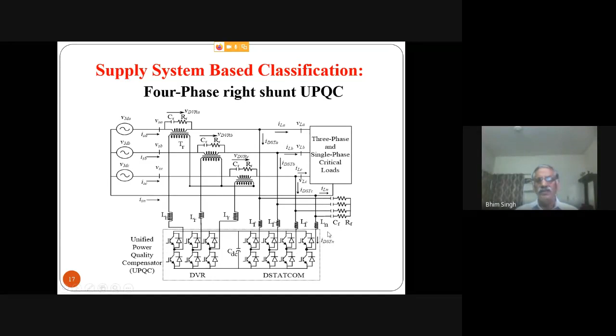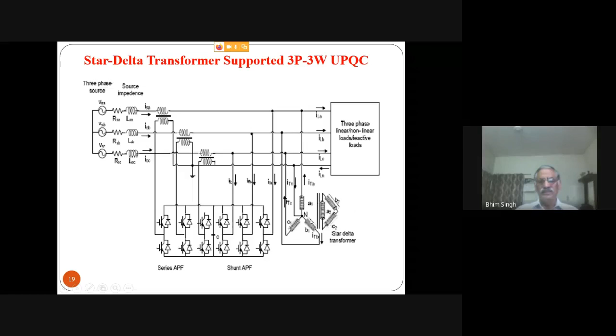But in a developing country, magnetics is much cheaper, so you can put a delta star. So this takes care of your triplen harmonics. The neutral current compensation is provided here, or you might have a zigzag to provide the local neutral. Also it is not necessary to take the neutral from the supply, but you can generate the neutral locally here. It means you might have a load 3-phase 4 wire, but the supply neutral is not there. Sometimes the neutral conductor gets busted, so you can create the local neutral with the help of zigzag here.